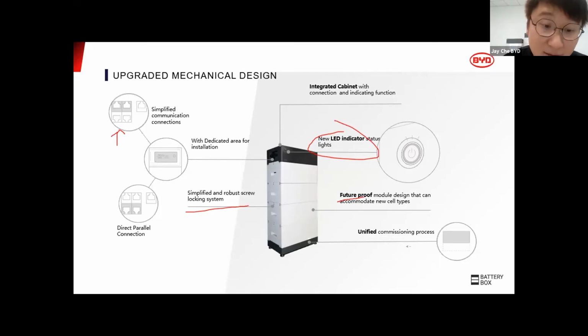Also, the size of the batteries is larger now, so you don't have to put 7 or 8 batteries, just putting them one by one. Now you have fewer boxes and larger batteries, and it should be able to handle one battery per installer - it's 40 kilograms. We're talking about the HVM battery here, and we recommend 2 installers, but 1 installer is fine if you're really strong - that's not an issue.